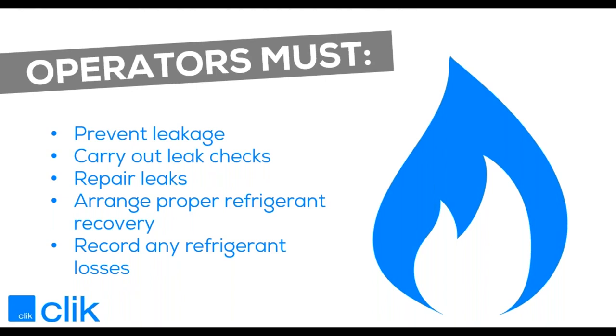Under the FGAS regulations it is now a criminal offense to release FGAS into the atmosphere. Most of the key obligations are the responsibility of the operator, defined as the natural or legal person exercising actual power over the technical functionings of the equipment and systems. Operators of equipment containing FGAS must prevent leakage, ensure that leak checks are carried out, repair any leaks as soon as possible, arrange proper refrigerant recovery, and maintain a record of refrigerant losses, additions, and servicing for each and every machine.